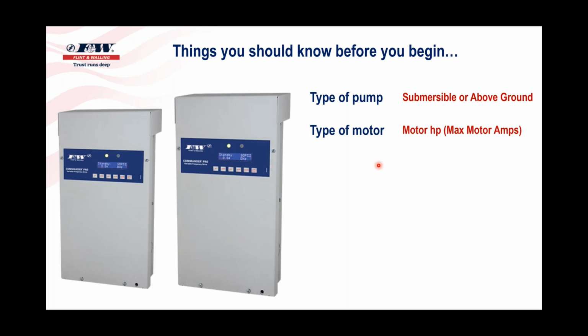When it comes to the type of motor, what we're really looking for there is horsepower. What horsepower of motor is this drive going to operate? Now, when you purchase a 1.5-horse drive, that's going to leave the factory set up to operate a 1.5-horse motor. Same with the 2, 3, and the 5. But if you have a 3-horse drive and you want to operate a 2-horse motor or a 1.5-horse motor, you're going to have to tell that drive what horsepower motor it's expected to operate.